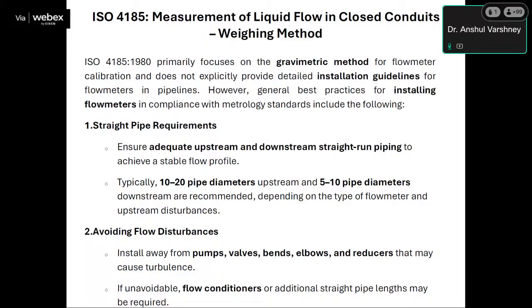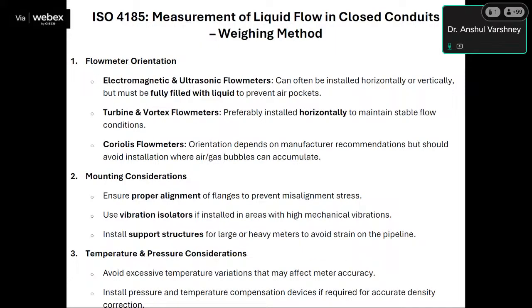Avoiding flow disturbance. Basically, the flow meters should be installed away from pumps, valves, bends, elbows, and reducers that may cause turbulence. If it is not possible to install away from these devices, flow conditioners or additional straight pipe lengths may be required for accurate measurement. The next point is orientation of flow meters. Electromagnetic and ultrasonic flow meters can often be installed horizontally or vertically, but must be fully filled with liquid to prevent air pockets.